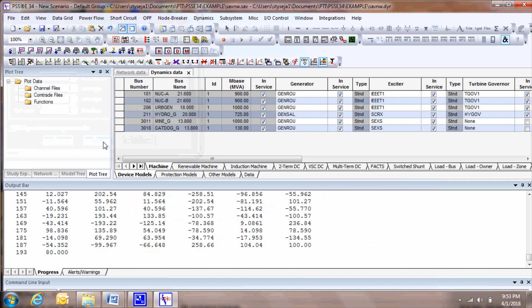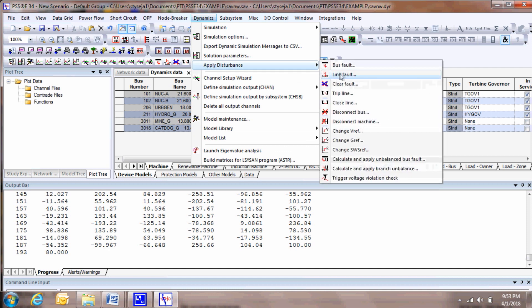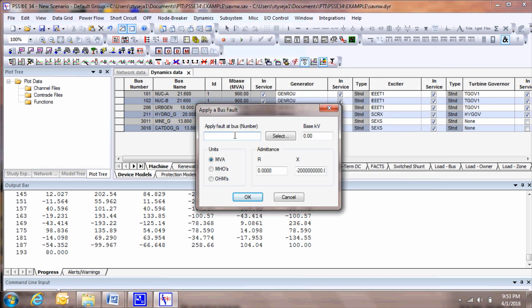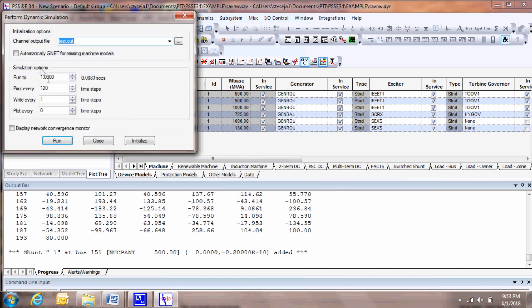To apply disturbance, go to Dynamics, Apply Disturbance. We will apply a six-cycle, three-phase bus fault at Bus 151. Run with the fault for six cycles, and then clear it.